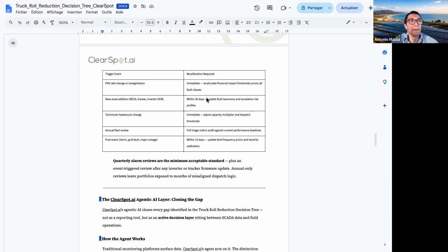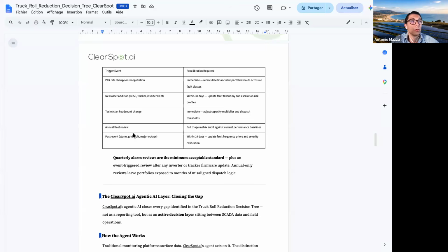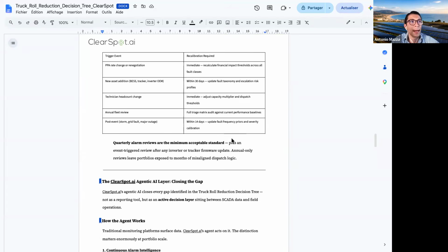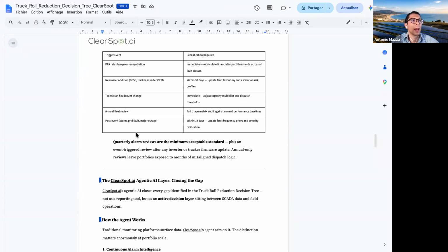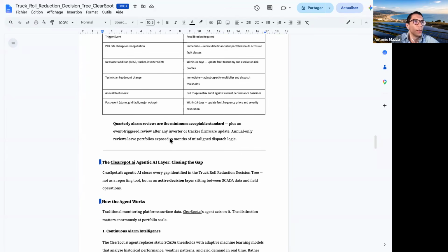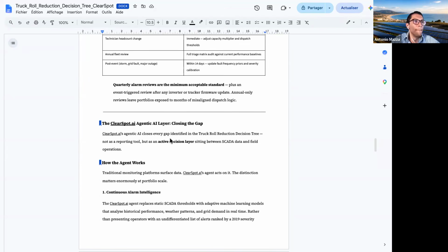Recalibration required for a PPA change should be immediate. New asset addition: within 30 days. Technician headcount change: immediate, adjust the capacity multiplier and dispatch threshold. Annual fleet review: full triage matrix adjustment, audited against the current performance baseline. And for post-events like a storm, grid fault or major outage: within 14 days. So it's updated for the fault frequency priors and the severity calibration.